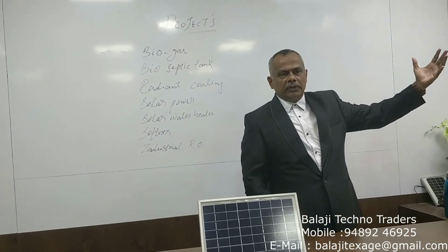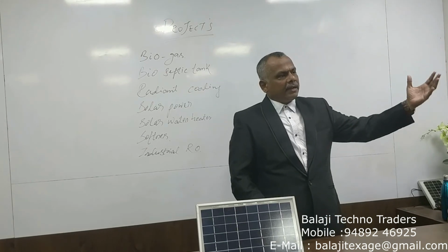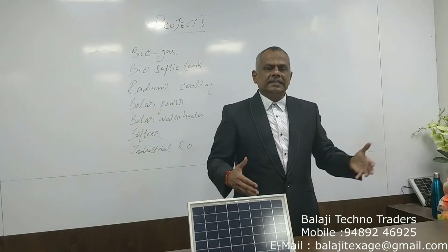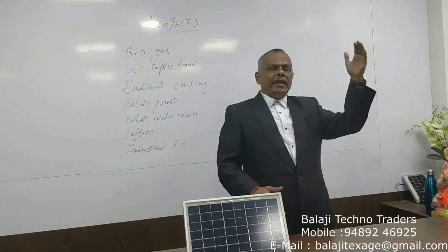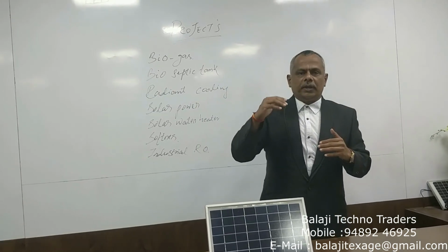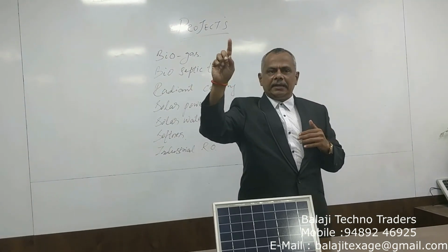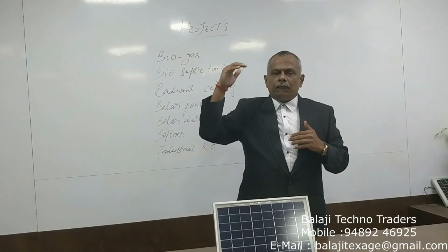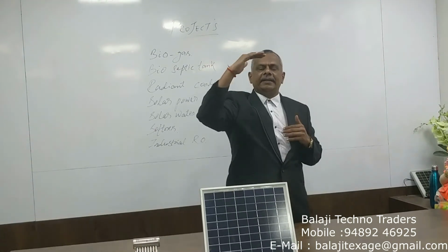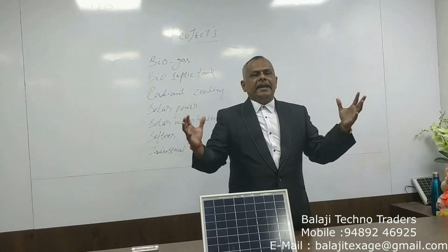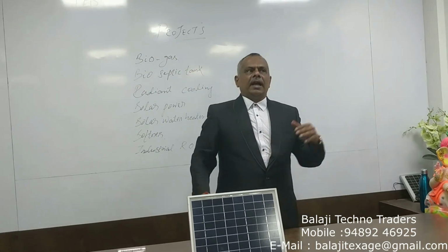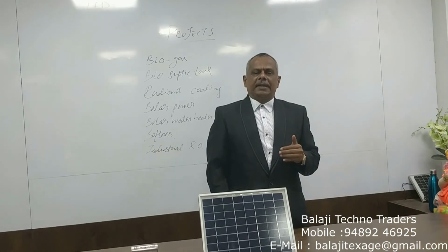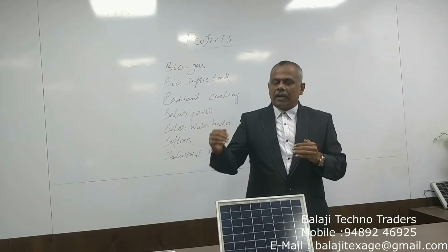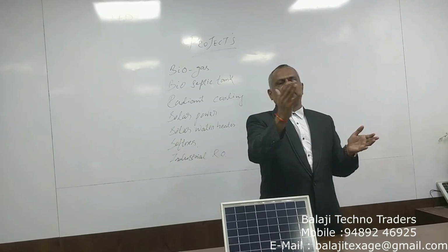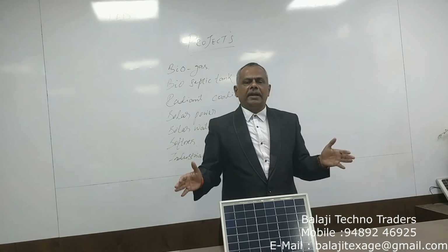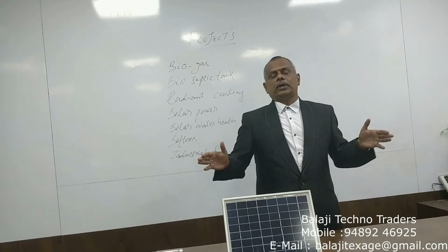When cement absorbs heat from the sun, it radiates that heat inside the building, creating heat indoors. So with radiant cooling, we lay a pipeline on the roof connected to a cooling tower. From the cooling tower, water circulates through the entire building, and the building's heat is carried away through the cooling tower. With the wet bulb temperature of the water around 20 to 21 degrees, through the transfer line, we can maintain the room at 25 to 27 degrees without an air conditioner.